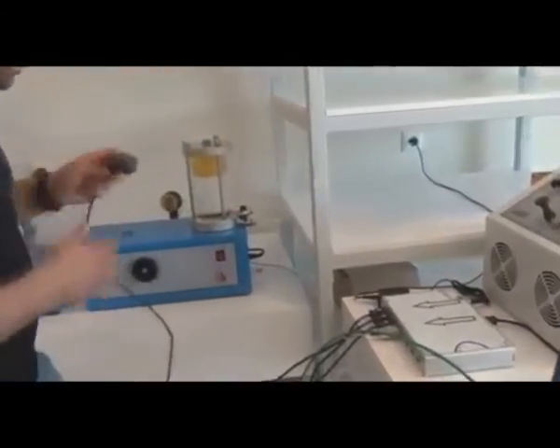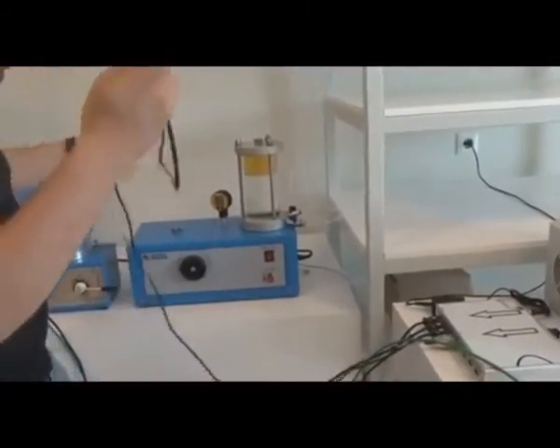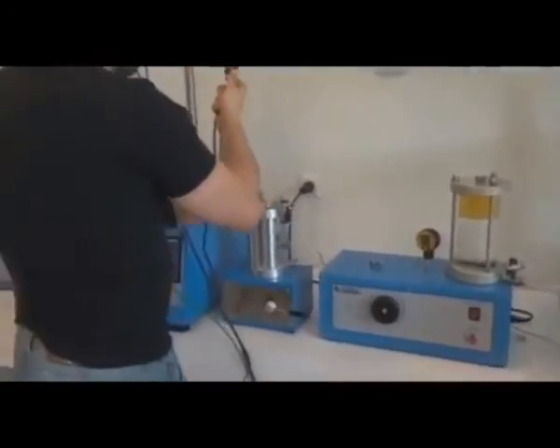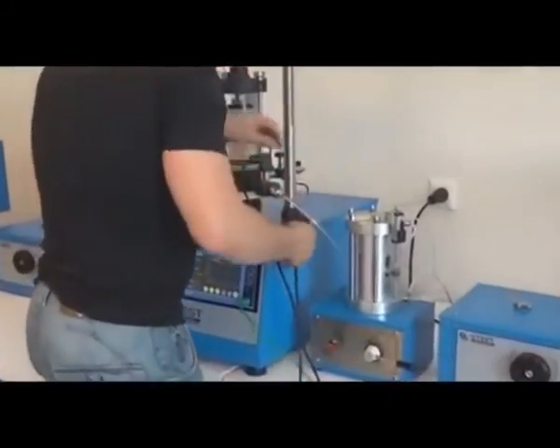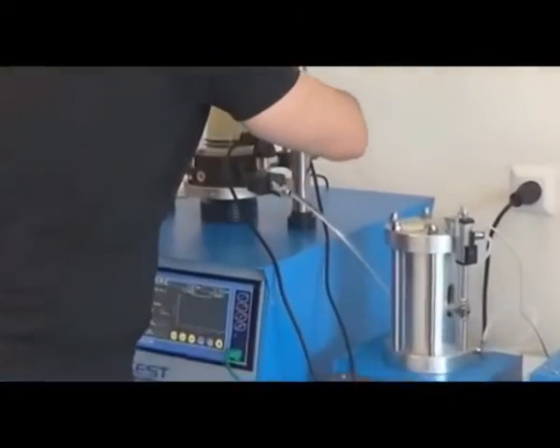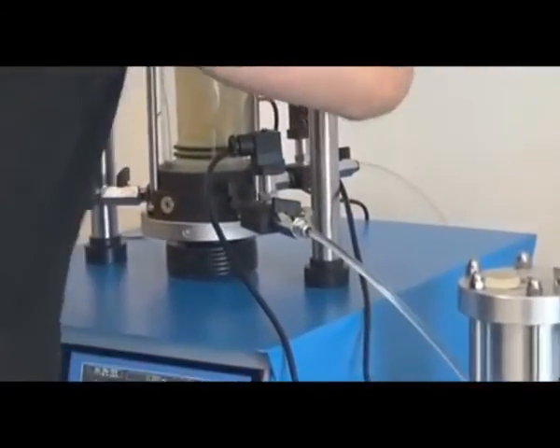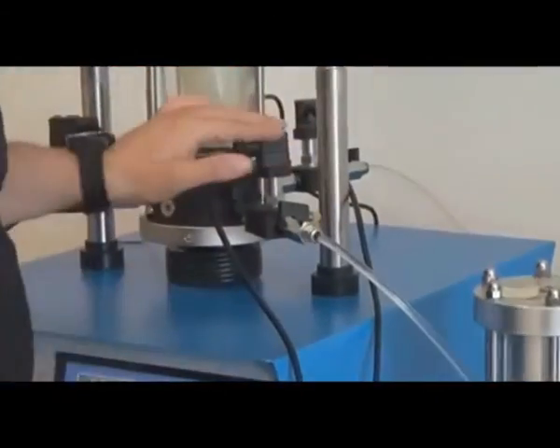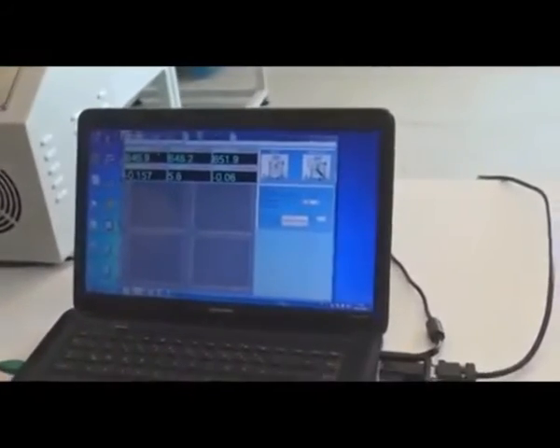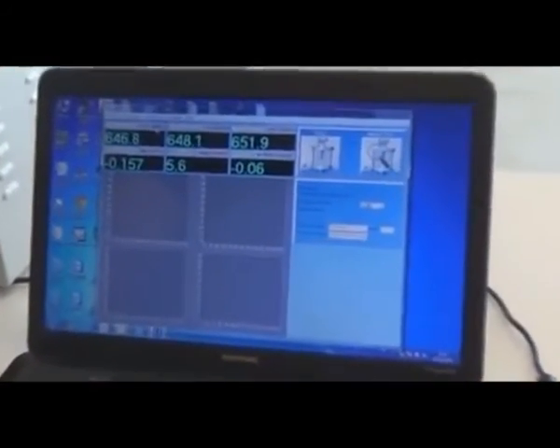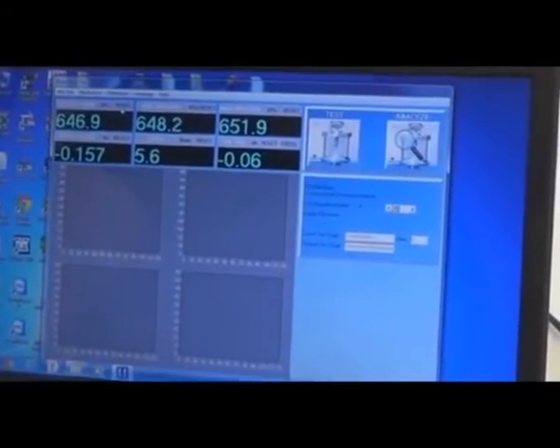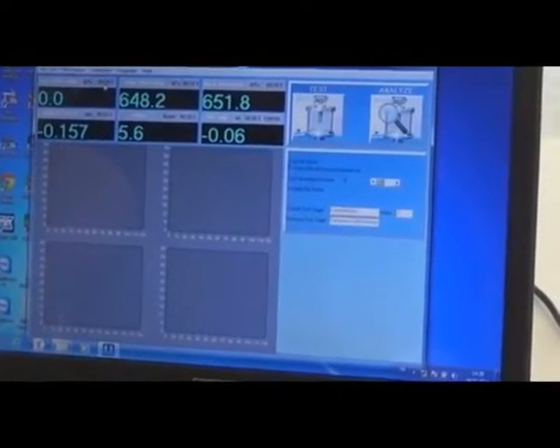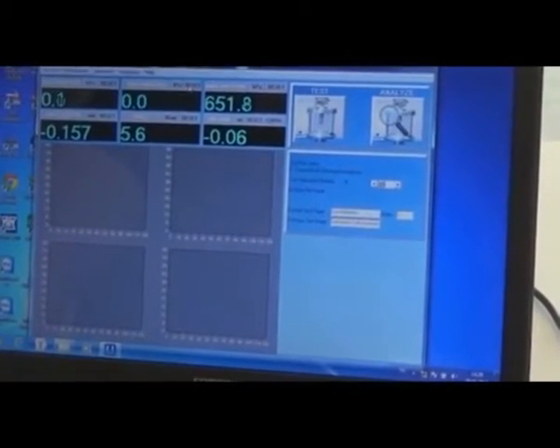And finally, the third channel is for the back pressure transducer, and the third cable is going to be connected to the back pressure transducer. Okay, on the screen we are seeing some meaningless values because it is just connected, and it is not yet calibrated. Therefore we are going to just reset the initial values.